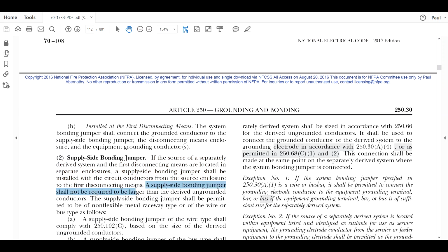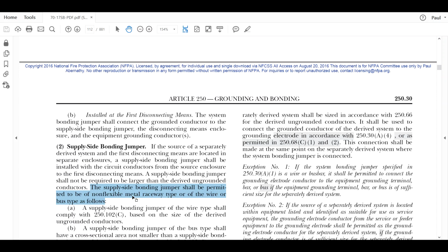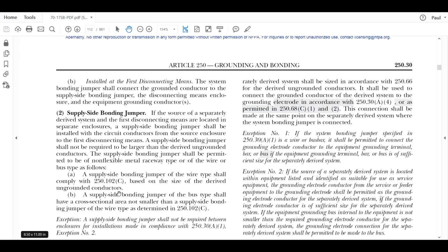It says a supply side bonding jumper shall not be required to be larger than the derived ungrounded conductors. In our case the derived ones were 350 kcmil, so it doesn't have to be larger than that. I can promise you it won't be. It says the supply side bonding jumper shall be permitted to be of the non-flexible metal raceway type, or of the wire or bus bar type. Well, in our case, we used a wire because the EMT also went to FMC, and the FMC is not a non-flexible metal raceway. It is a flexible metal raceway, obviously by the name. It's a flexible metal conduit, if you will. So if it was all EMT, then I could get away with not having to put a supply side jumper in it. But it's not, so I do. So we're going to use the wire type.